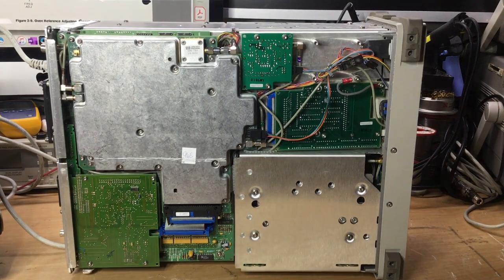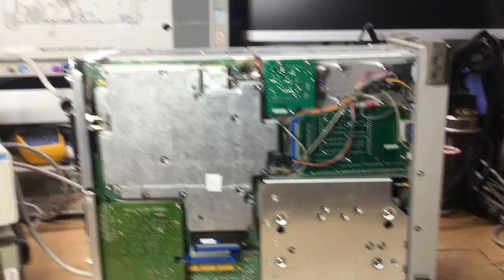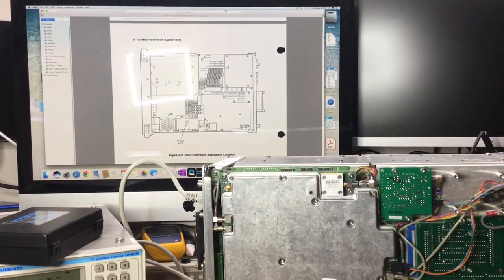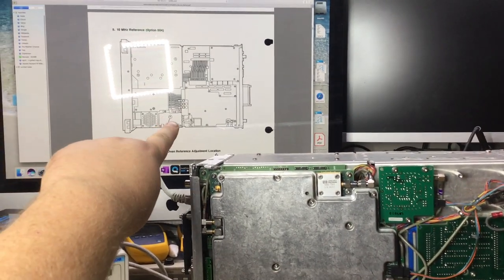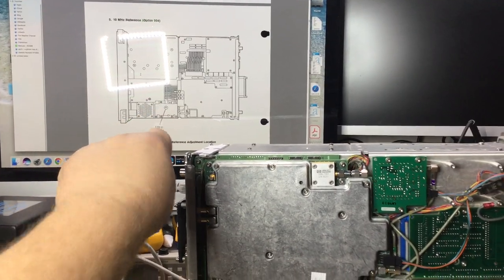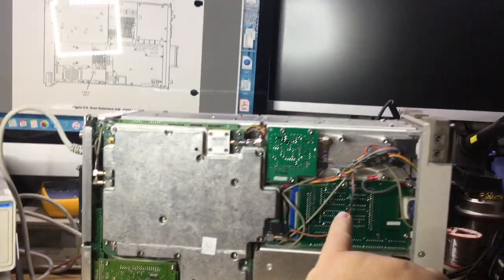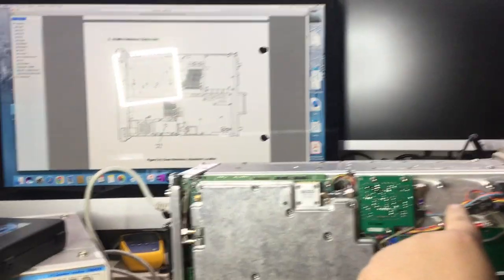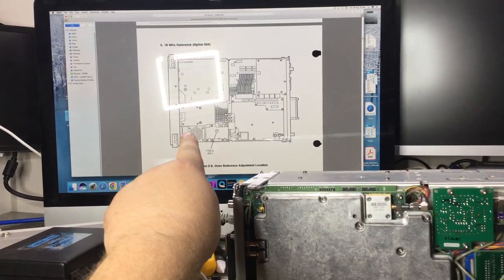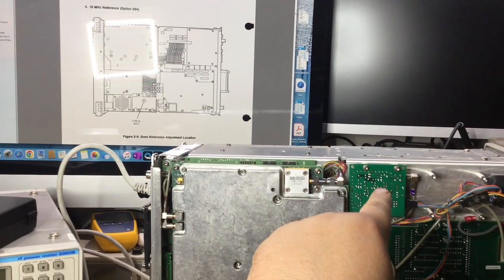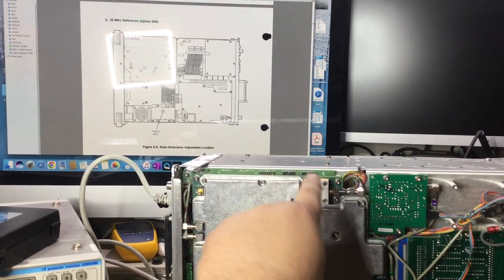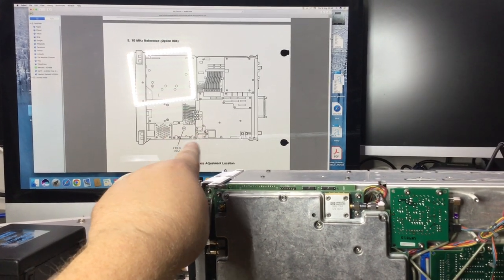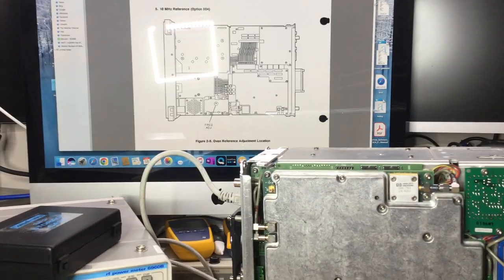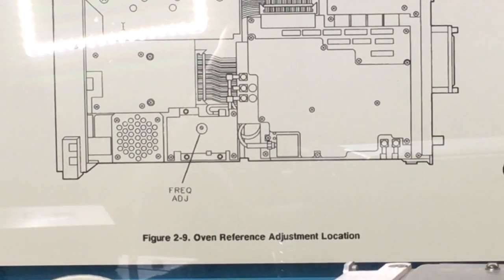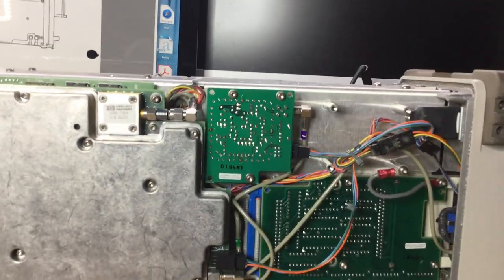Okay, so we're on the underside of the instrument now, and according to the diagram, it shows the 10 meg reference oscillator to be here in this area. So it's like reverse, so this would be where the speaker grill is if it had the speaker option, which is this grill here. Then with the option board, the YIG, I believe, oscillator. So we've got this, what appears to be a frequency adjust, it says there. But there ain't no frequency adjust on this one. So it looks like it's done through software, through the calibrate.